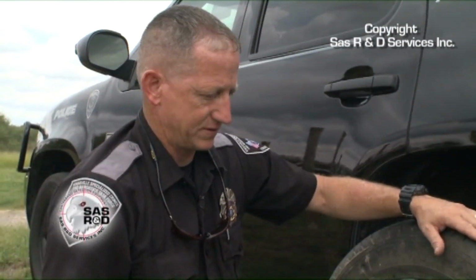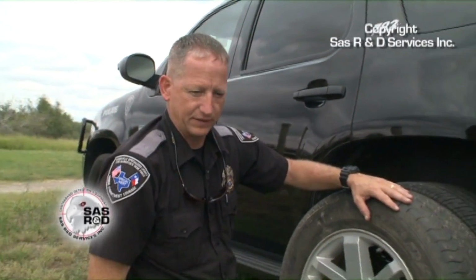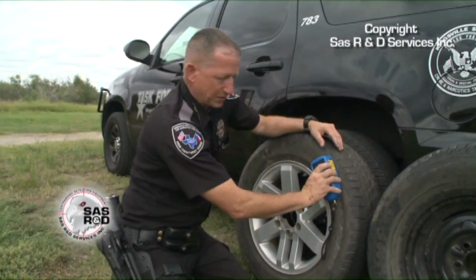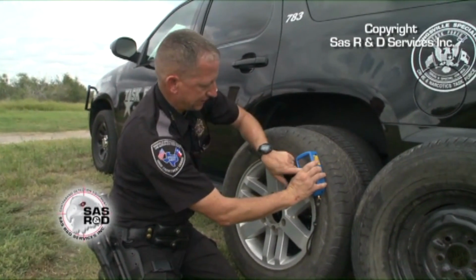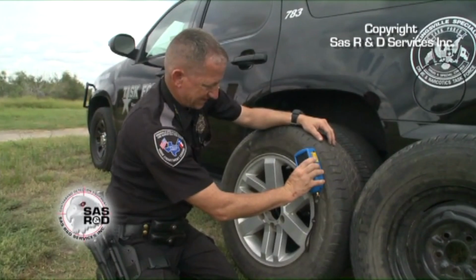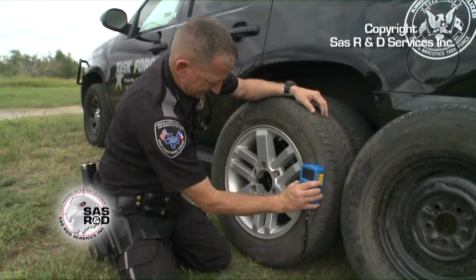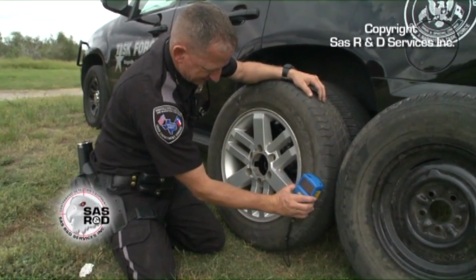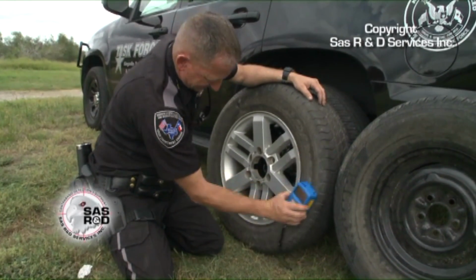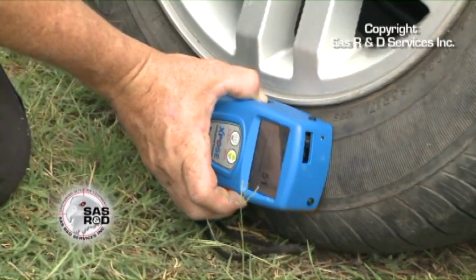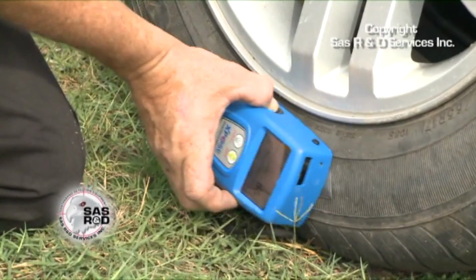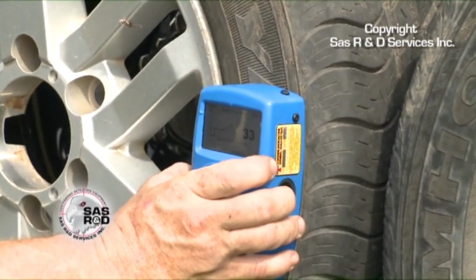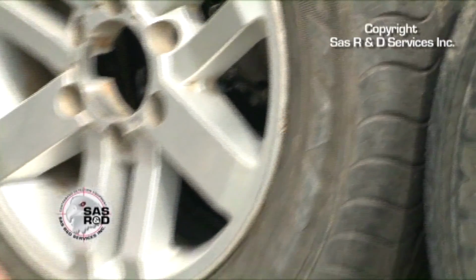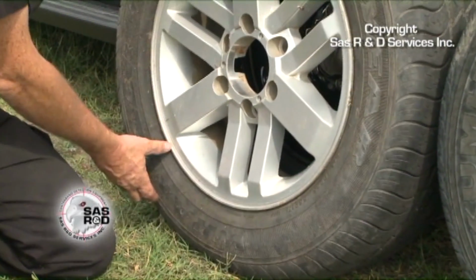Now we're going to show you a change in density on a suspect tire that has contraband in it. For the purpose of this example, we're going to go ahead and place it in zero scan mode. And begin changing 36, 33. Right here we have a change in the graph, plus the audible signal, and it's in about the high 50s and 60s. And we turn back up here to the top of the tire, we return back to the low 20s. This would indicate that there is contraband located in the bottom half section of this tire.